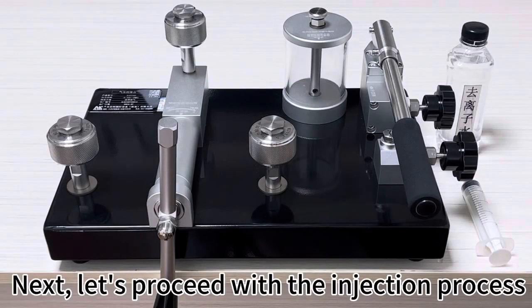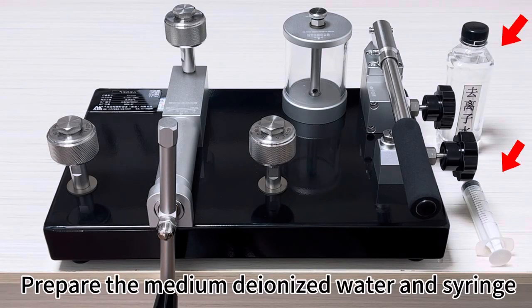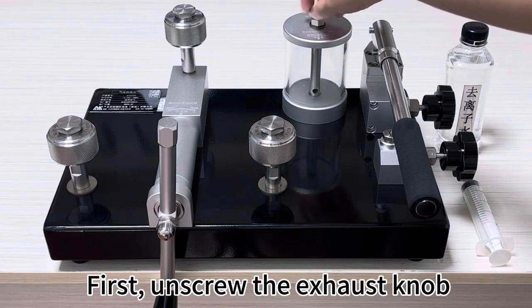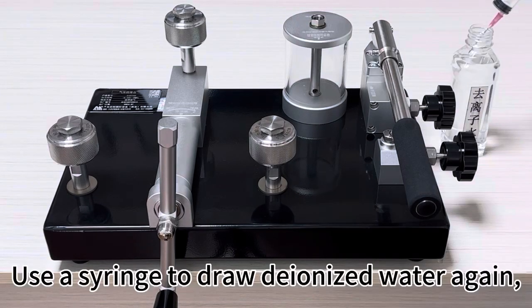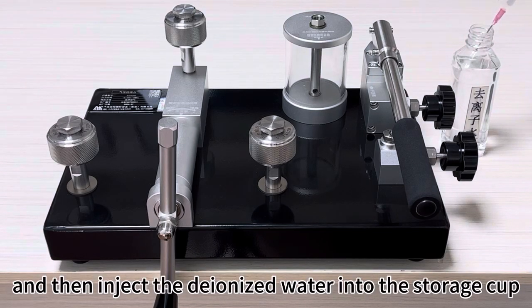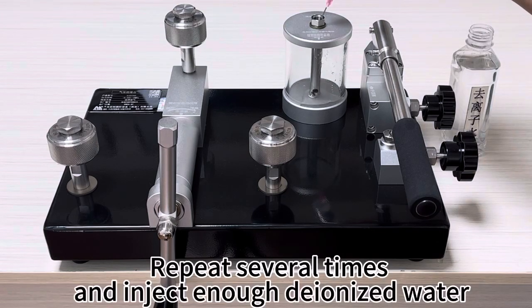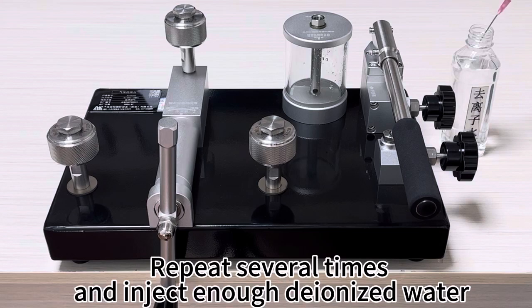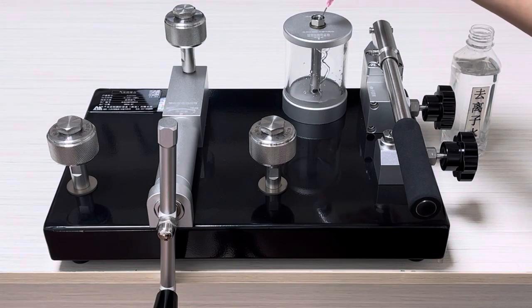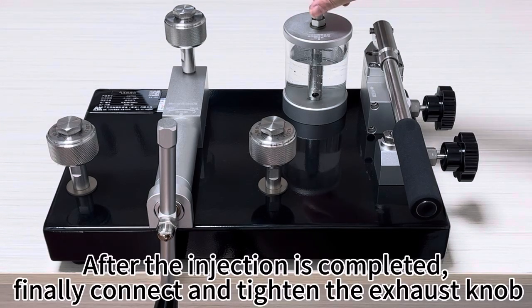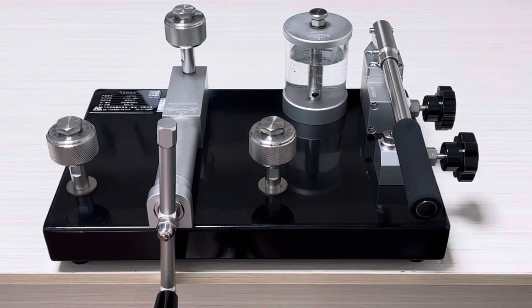Next, let's proceed with the injection process. Prepare the medium deionized water and syringe. First, unscrew the exhaust knob. Use a syringe to draw deionized water, and then inject the deionized water into the storage cup. Repeat several times and inject enough deionized water. After the injection is completed, finally connect and tighten the exhaust knob.